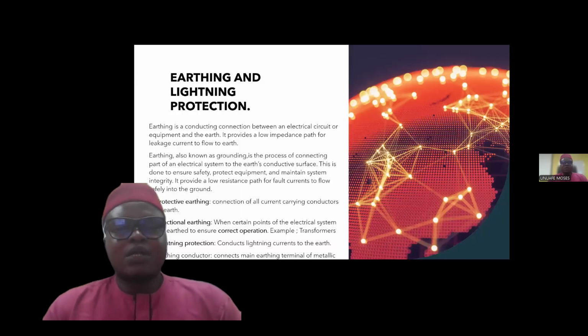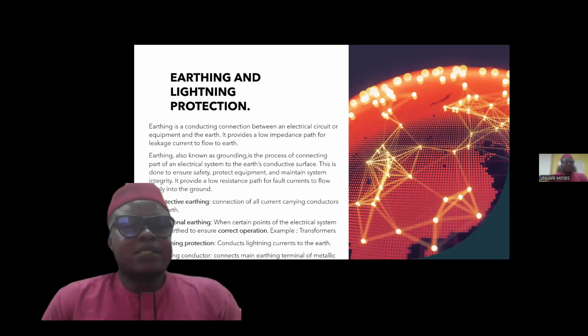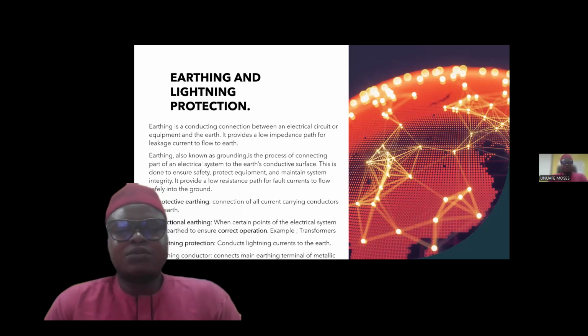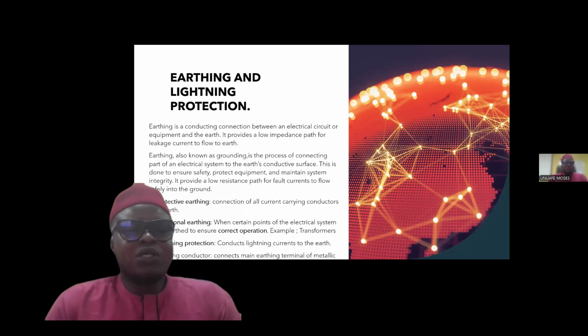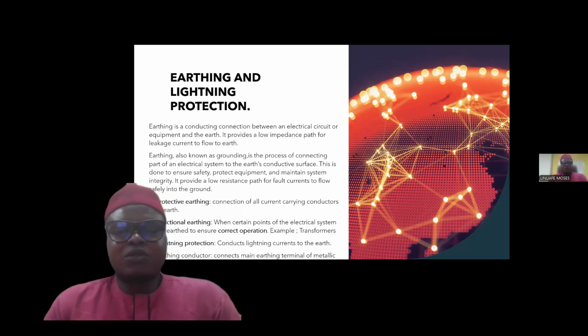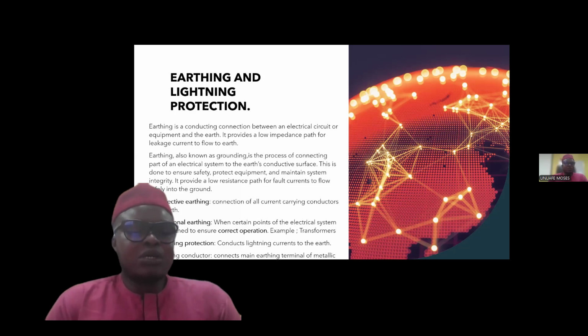Now, I want you to understand that earthing is a conductive connection between an electrical circuit or equipment and the earth. It provides a low impedance path for leakage current to flow to the earth. Earthing, also known as grounding, is the process of connecting part of an electrical system to the earth conductive surface. This is done to ensure safety, protect equipment, and maintain system integrity. It provides a low resistance path for part of a fault current to flow safely into the ground.